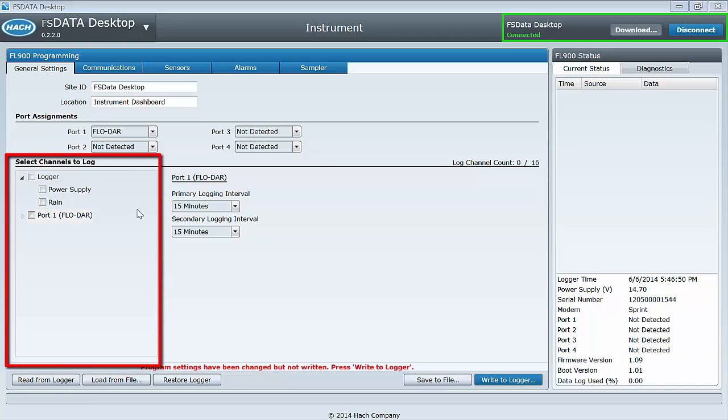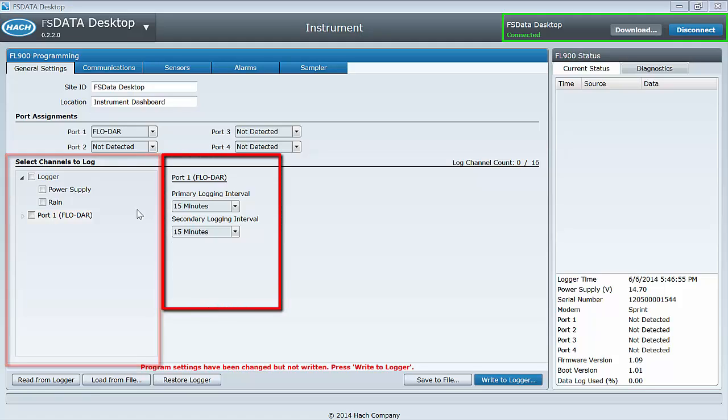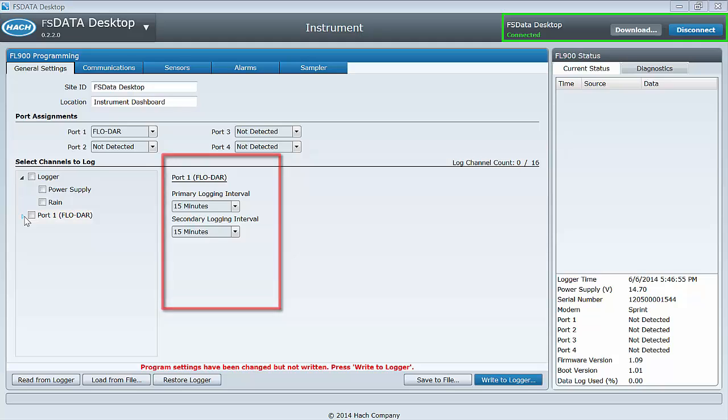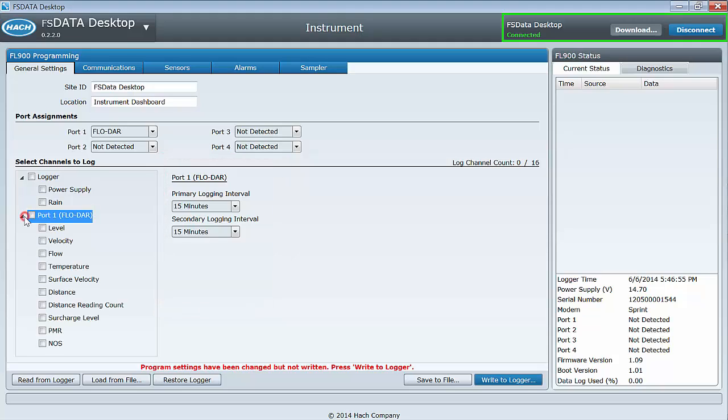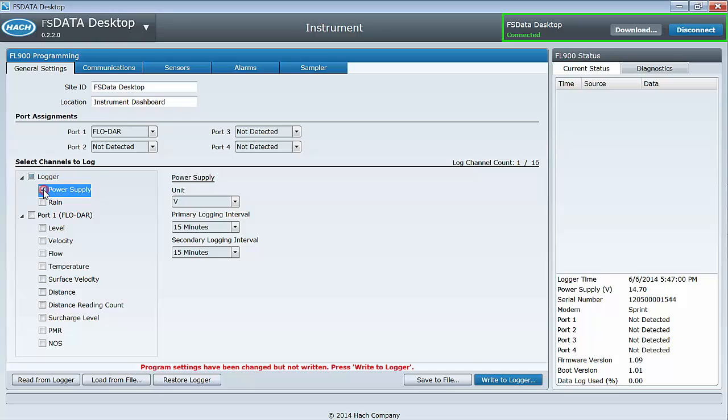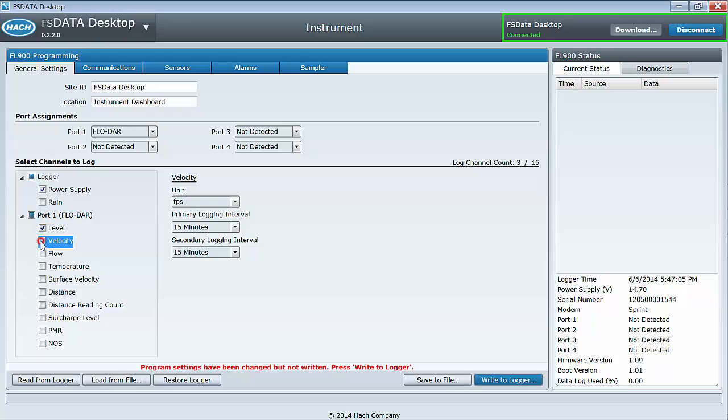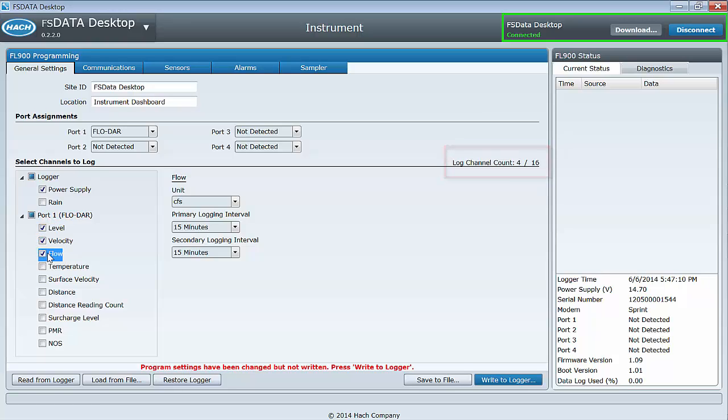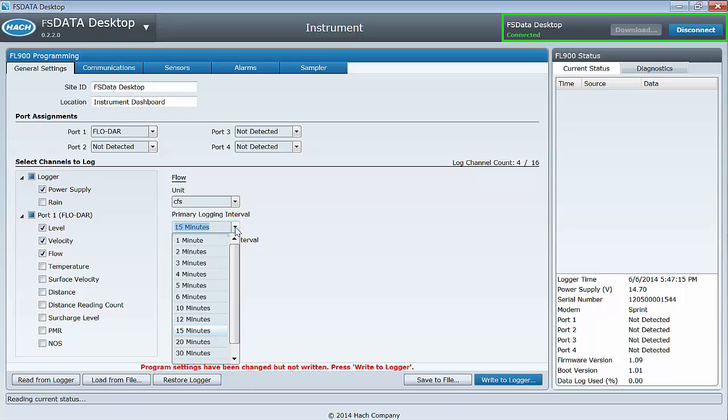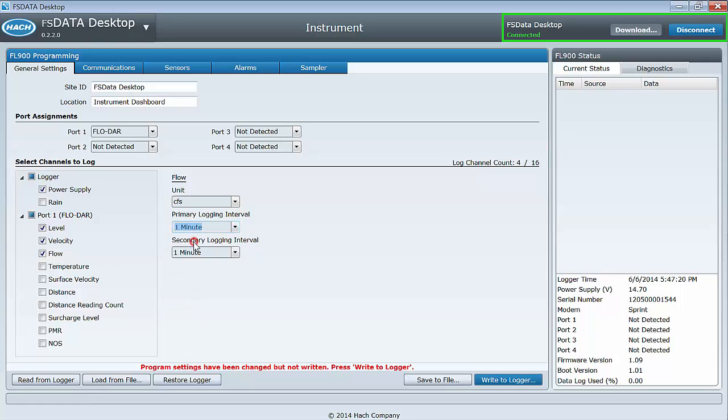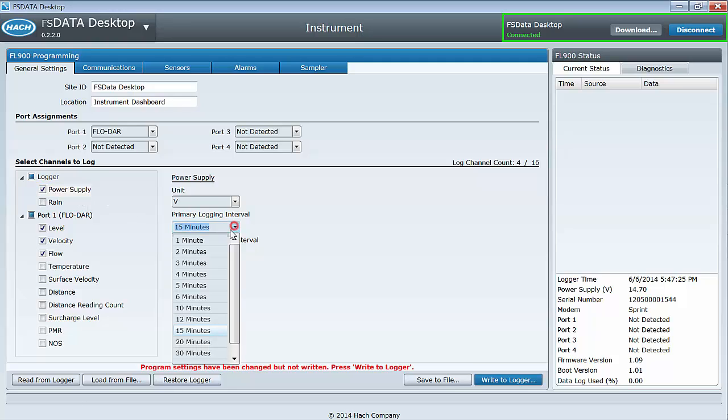Beneath the port assignments, you select the channels to data log and the data logging interval. Expand the list by selecting the triangle on the left of the label and then selecting the channels by clicking the boxes. You can data log up to 16 channels and there is a channel counter on the right. The instrument power supply voltage, rain, and sensor logging interval can be set independently.